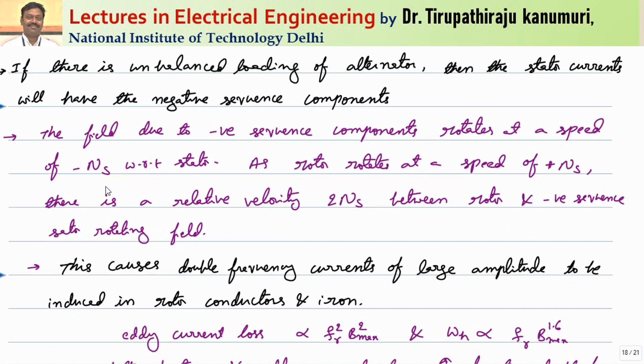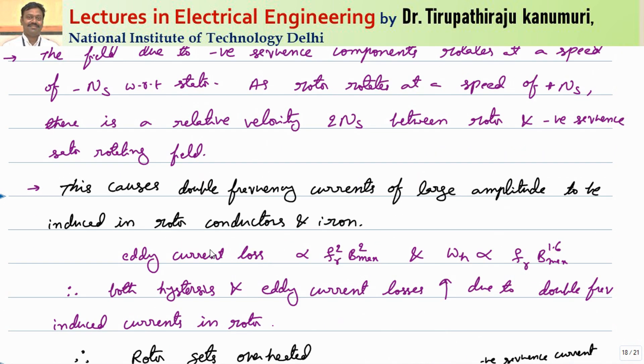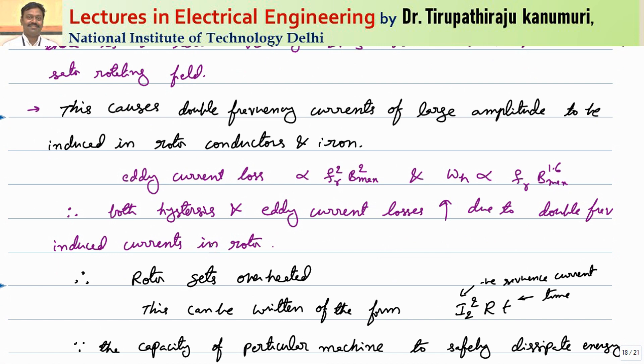To summarize: if there is unbalanced loading of the alternator, the stator currents will have a negative sequence component. The field due to the negative sequence component rotates at minus ns with respect to the stator. Since the rotor rotates at plus ns, there is a relative velocity of 2ns between the rotor and the negative sequence stator rotating field. This causes double-frequency currents of large amplitude to be induced in the rotor conductors and iron.